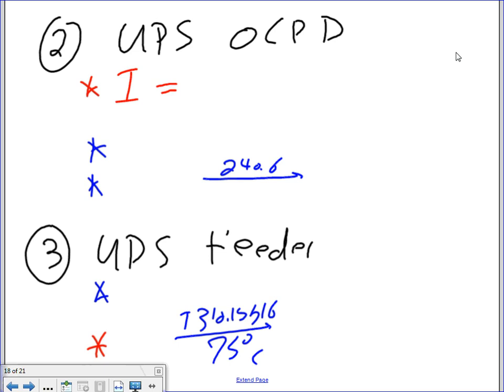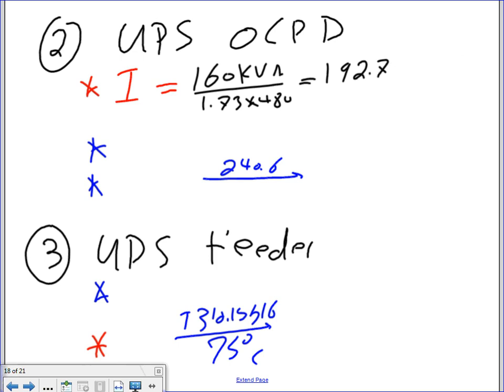So let's go size. The second thing, I have 160 kVA divided by 1.73 times 480. I don't have the answer, so I need you guys to help me. 192.7. 192.7 approximate, right? What did you say, Karen? She said 192.45. Maybe it's just approximation because of the 1.73. Let's stick with that one, and then you're going to go next with 1.25.